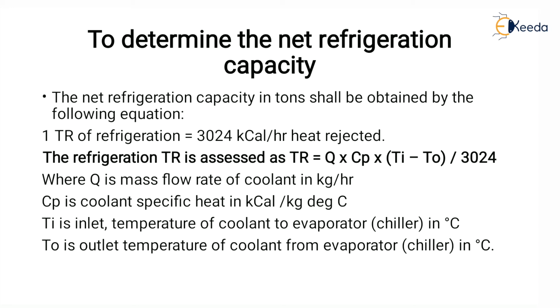Where Q is the mass flow rate of coolant in kg per hour, Cp is the coolant specific heat in kilocalorie per kg degree Celsius, Ti is the inlet temperature of the coolant to the evaporator in degree Celsius, and To is the outlet temperature of coolant from the evaporator in degree Celsius.